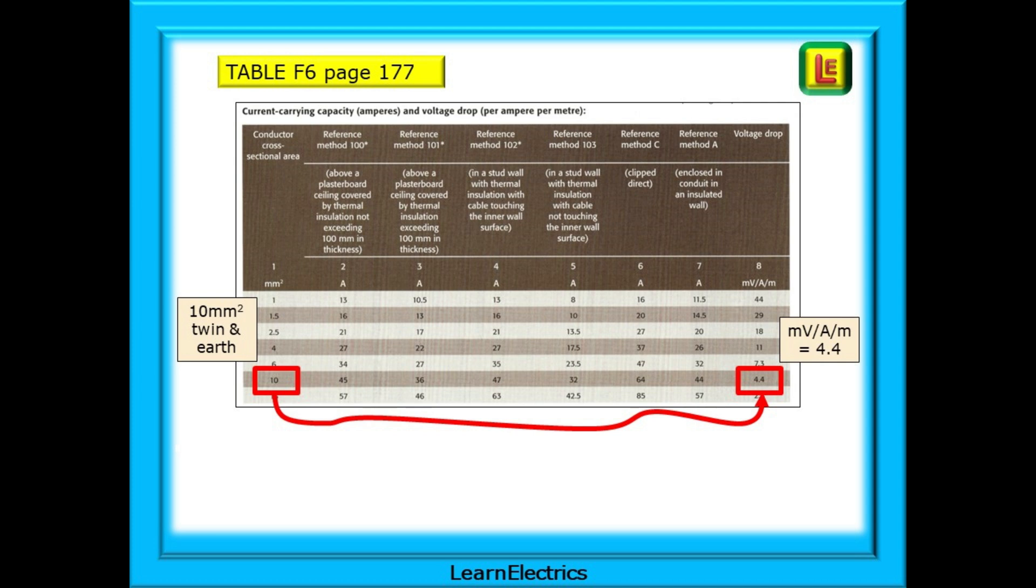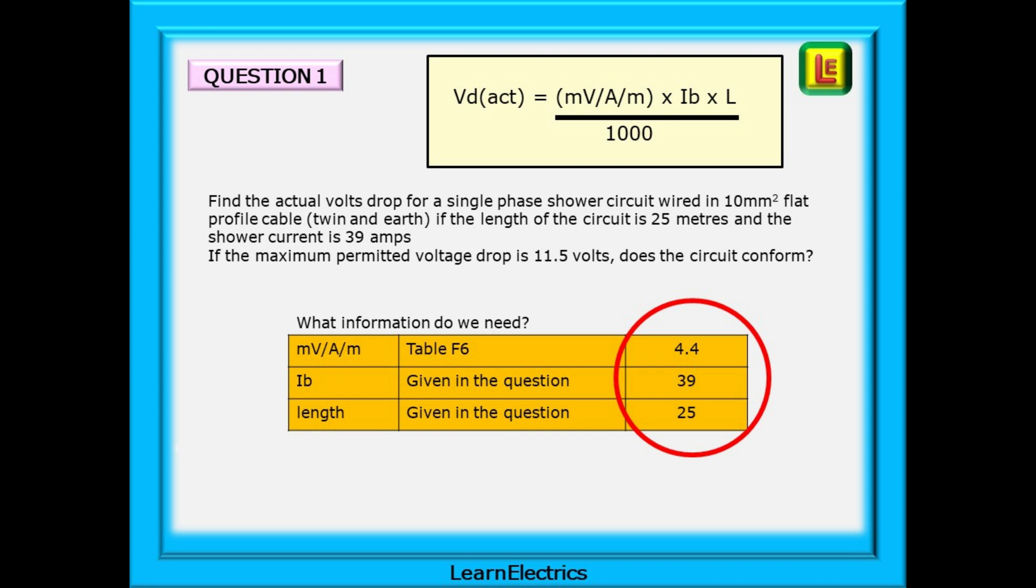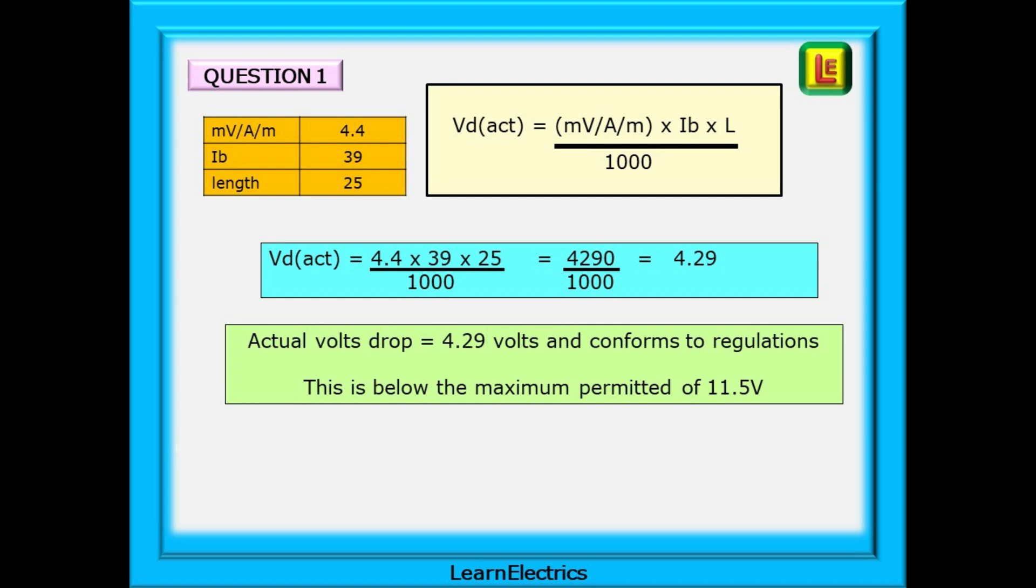I always make a small chart or list of the information that I need to know before I can answer the question. And we need to know three things here. Table F6 on page 177 will give us the millivolts per amp per meter. While using 10mm cable, find this on the left and then move to the rightmost column and find 4.4. That is the MVAM number for 10mm copper conductor. IB and the length are given in the question and the rest is easy now. Put the numbers into the formula as shown and out pops the answer 4.29. The actual volts drop is 4.29 volts and conforms to regulations as this is below the maximum permitted voltage drop of 11.5 volts.